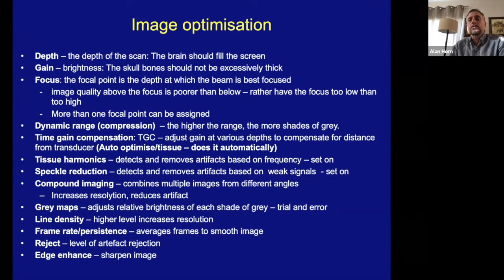The higher your line density, the higher your resolution, and the lower your frame rate. The frame rate persistence setting averages out frames to smooth the image. Then the reject setting is to reject artifact, and edge enhance is to sharpen the image. So as dull as it may seem to go through all those, they are enormous tools to actually provide an image that is useful to you.